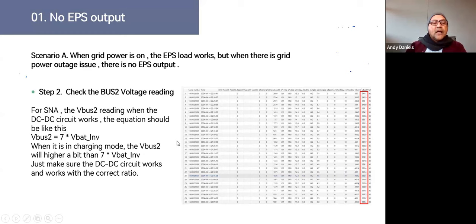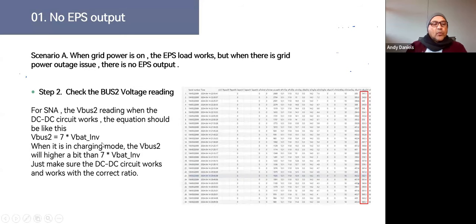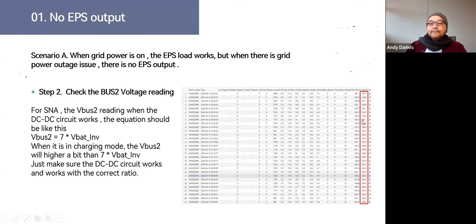If the BUS2 voltage is incorrect, it means the DC-to-DC circuit is not working and the machine will need to come in for repairs. To summarize: on the SNA6 the multiplier is 7 times the nominal battery voltage, and on the SNA5 it is 6 times. If this ratio is not correct, the DC-to-DC circuit is faulty.